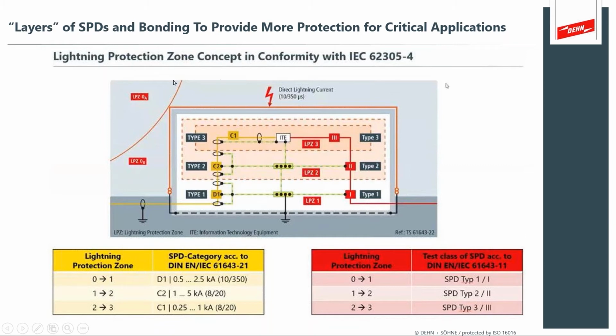You have your air terminals, you have your down conductor system, you have your earthing grid, you have bonding measures throughout the plant, and then you have surge protection measures that give you that complete control of the pillars of protection. You don't want to leave any of these measures disregarded. You could have side flash, you could have problems with your bonding where a cabinet isn't bonded, and then you'll have uncontrolled voltage rises. And that's the whole point. We're trying to control and divert the lightning currents and then give yourself these protected zones of coverage.